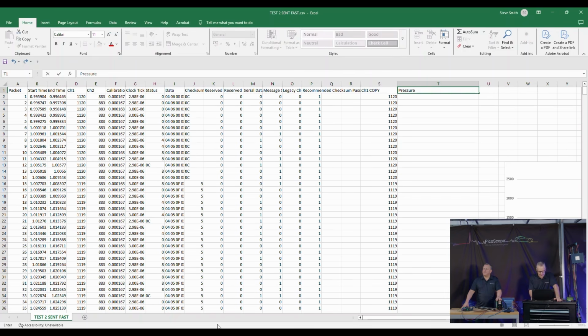What we're going to do is use an Excel sheet that carries a formula enabling you to use 2 data points and a linear equation. With 2 data points of a physical value, the pressure from the pressure transducer, and 2 encoded values, we can convert that, because we know the slope and the gradient, and how to graph this into a human readable value.